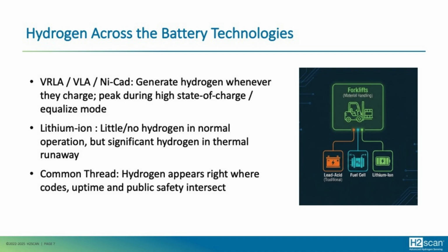Lithium batteries have no hydrogen that really comes out of them during normal operation, but if you overcharge the battery and they actually go into thermal runaway, then the vent gases can be released, and that's the beginning of thermal runaway. And about 50% of those vent gases would be hydrogen. And so you have a hydrogen risk there only in abnormal operations.